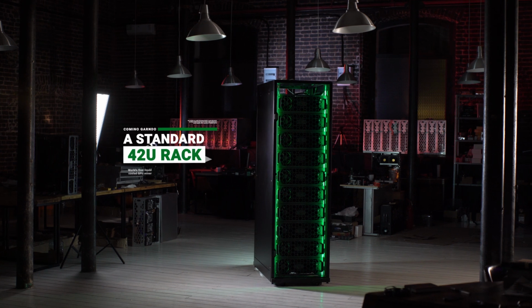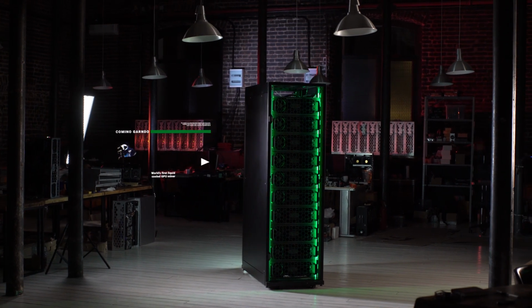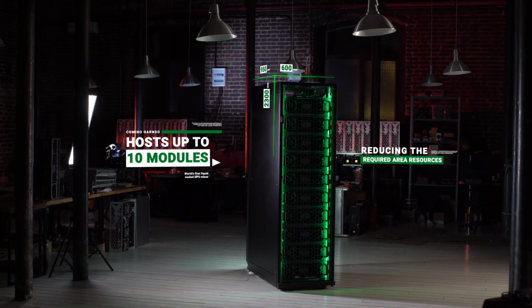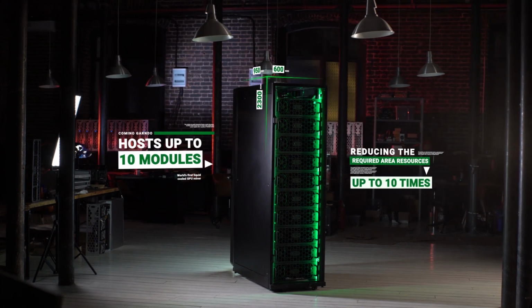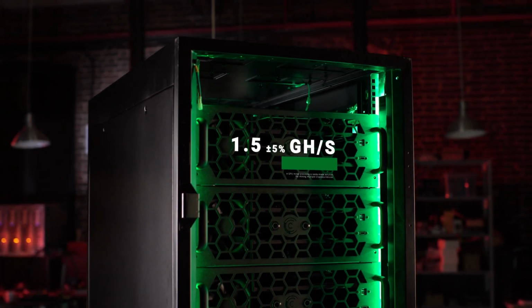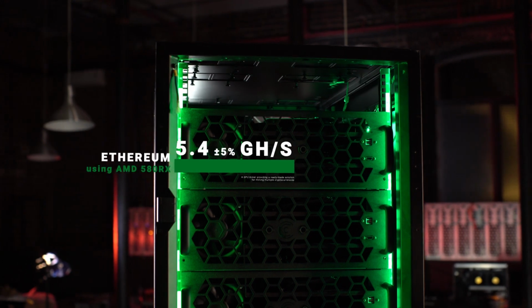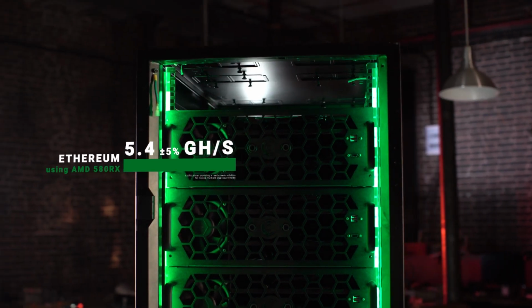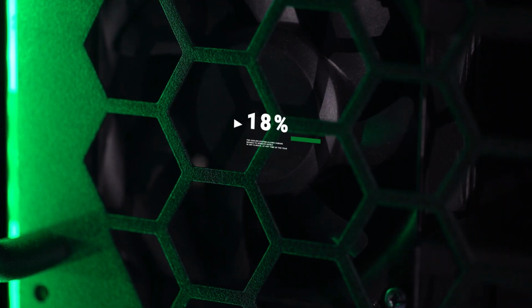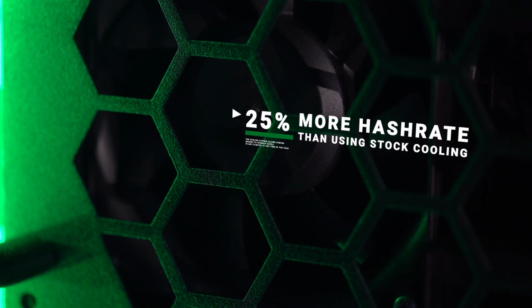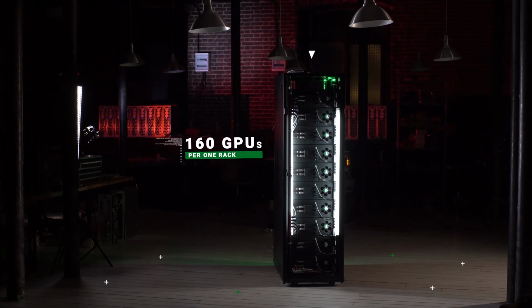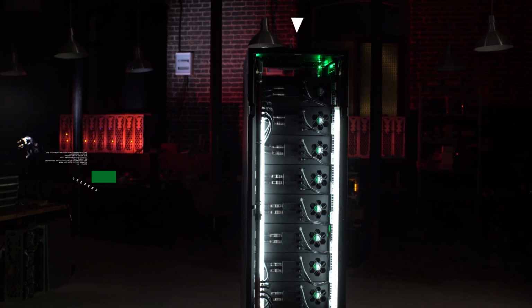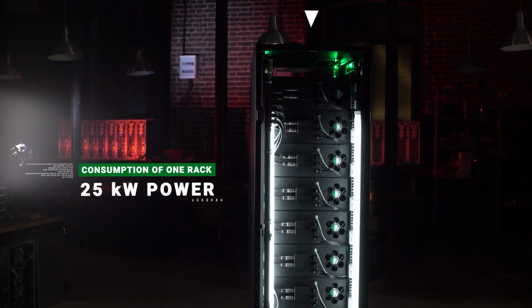A standard 42U rack hosts up to 10 modules, reducing the required area and resources up to 10 times. It delivers 1.5 GH/s on Ethereum using AMD RX 580 GPUs, 18% more than on air, with 160 GPUs per rack and 25 kilowatts power consumption per rack.